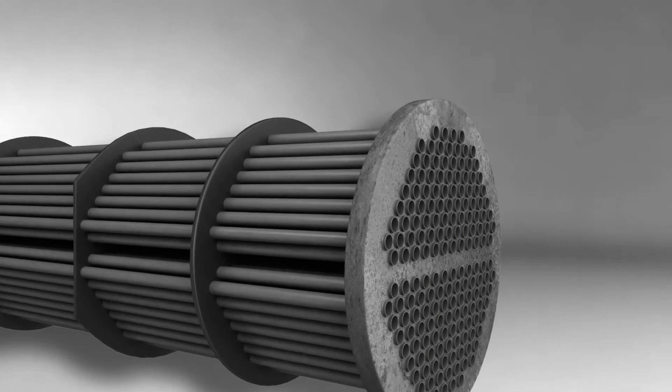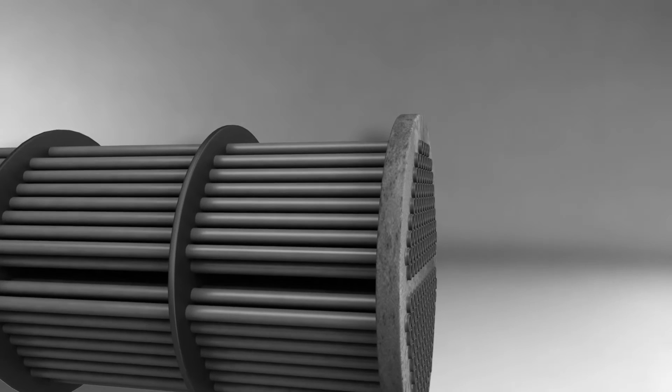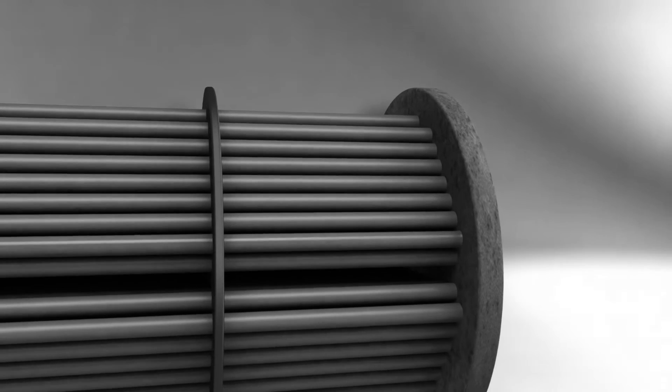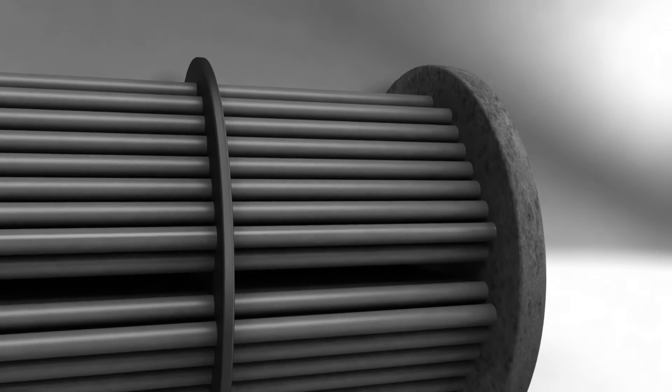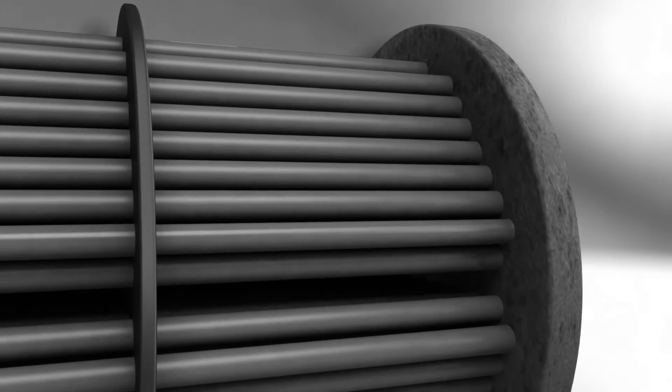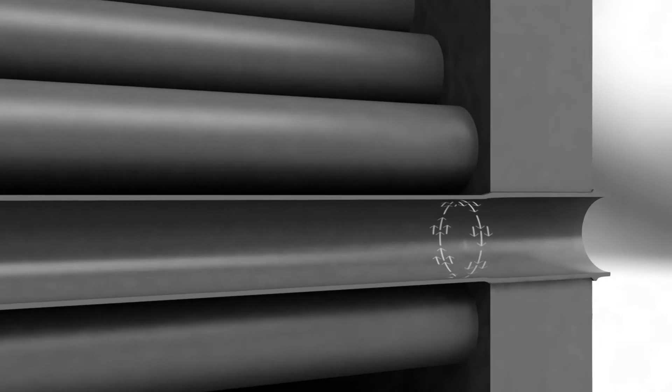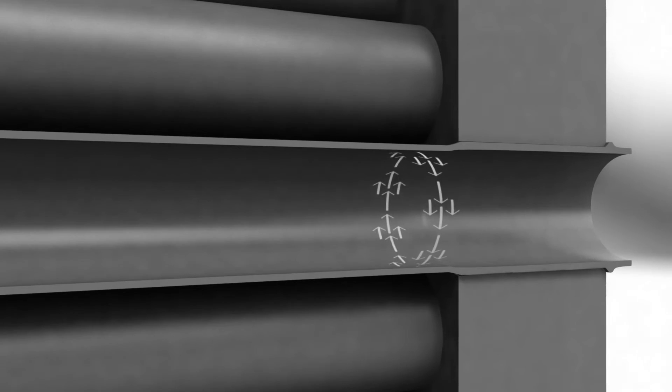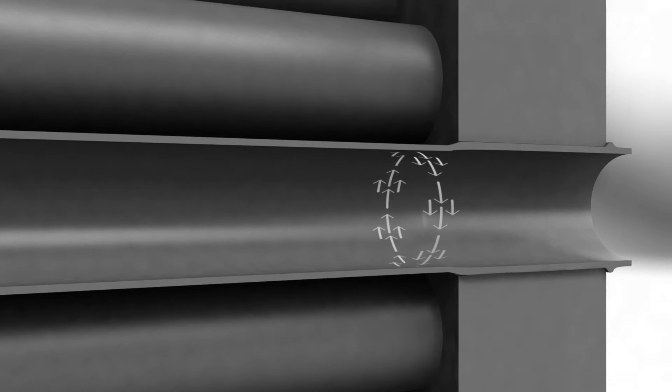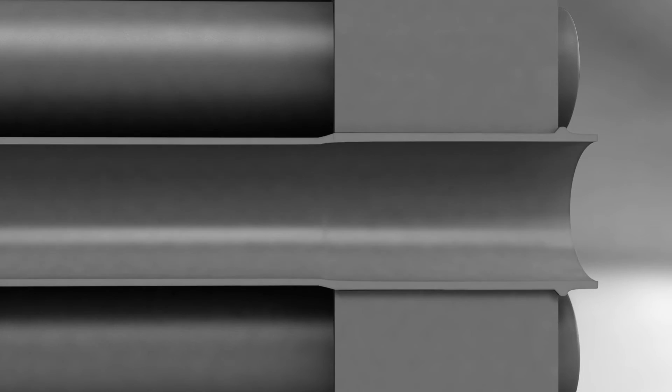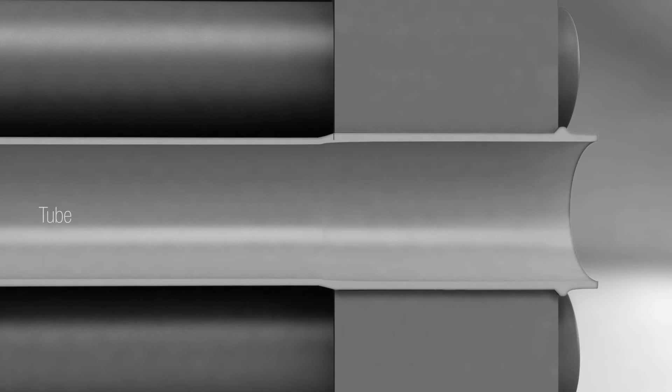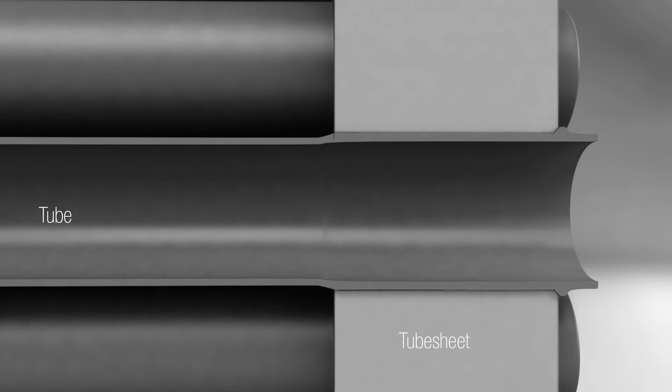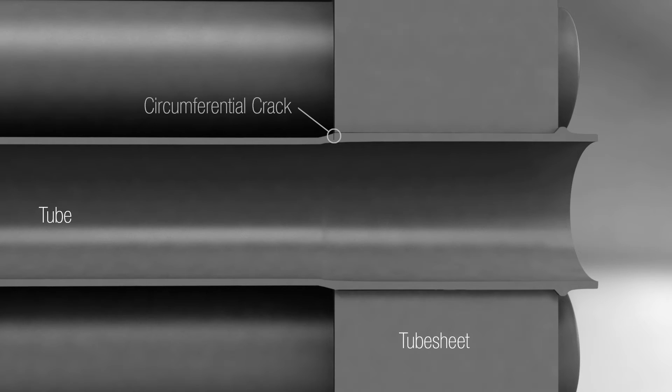Circumferential cracking is very difficult to detect and characterize with standard eddy current bobbin probes. That's mainly because eddy currents generated by bobbin probes flow parallel to circumferential cracks. Bobbin probes are also sensitive to ferromagnetic interference generated by tube sheets and support plates of heat exchangers. The large signals generated by these structures usually mask the small signals from circumferential cracks.